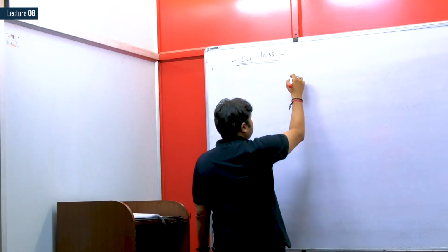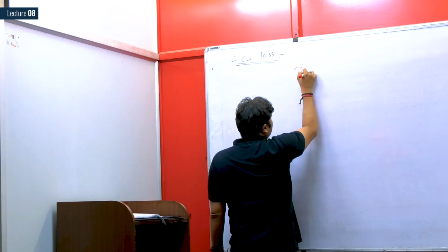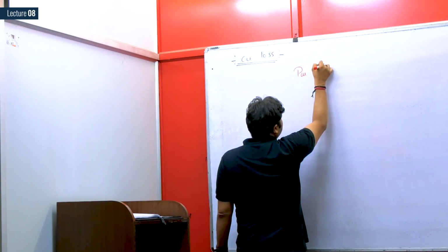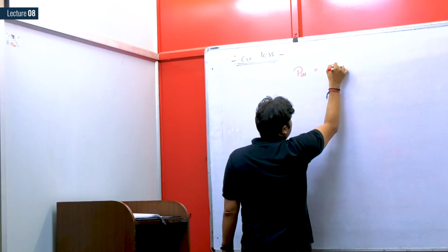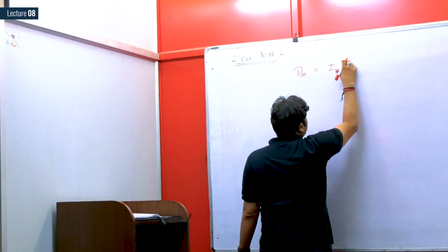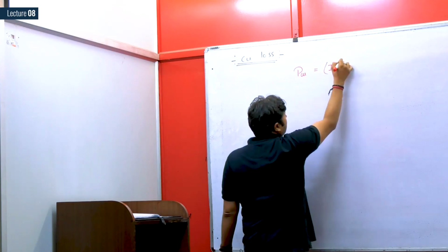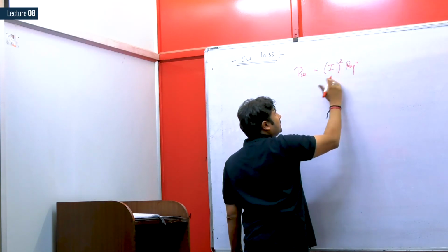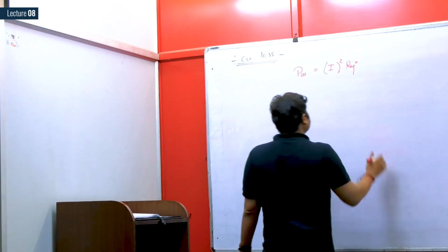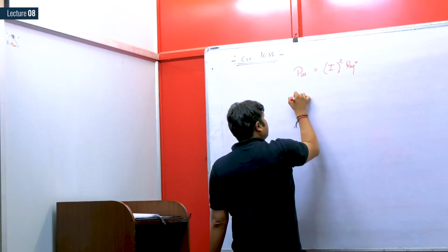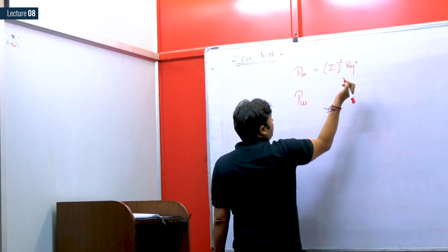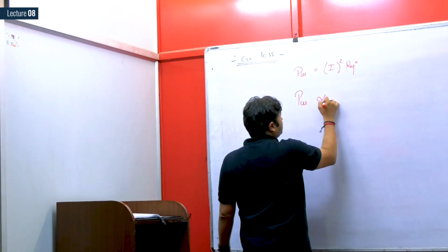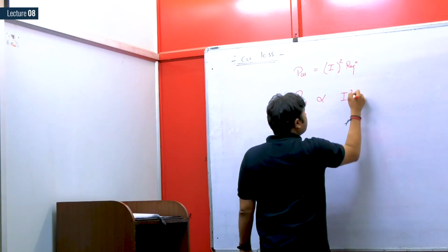Okay, now please see. So copper loss is what? Copper loss is proportional to, or equal to, I square R equivalent, where R equivalent is the equivalent resistance referred to either HV side or LV side. R equivalent is treated as a constant, as we have kept the temperature constant. So copper loss is now proportional to operating current square.